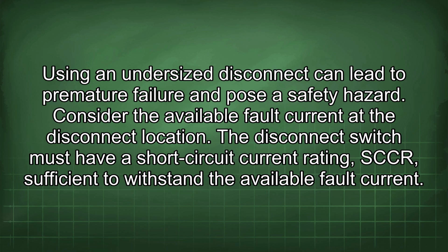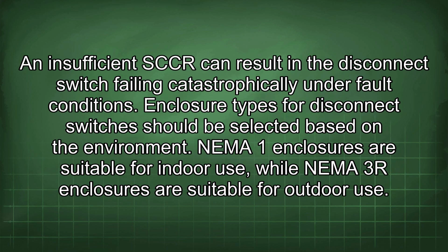Consider the available fault current at the disconnect location. The disconnect switch must have a short circuit current rating, SCCR, sufficient to withstand the available fault current. An insufficient SCCR can result in the disconnect switch failing catastrophically under fault conditions.